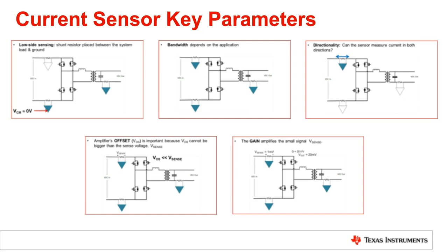An amplifier's offset is one of the most important things that's going to affect your accuracy inside the system. What it's defining is the smallest current you can sense, or the smallest voltage across that resistor inside the system. In addition to offset, what's going to be important is also the offset drift. This is commonly an overlooked parameter, and as system temperature changes, that drift can really impact the offset voltage and have a fairly significant effect on accuracy across a temperature range.